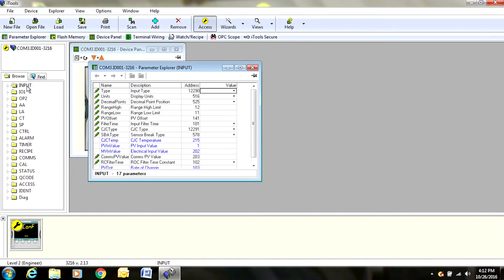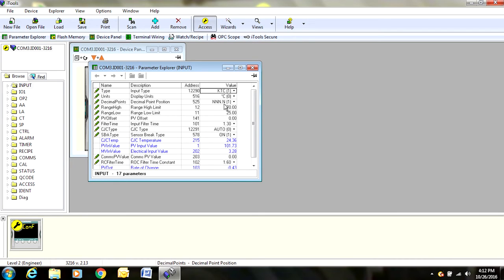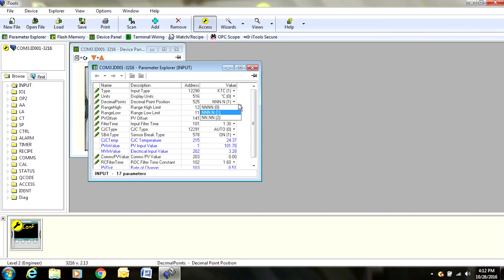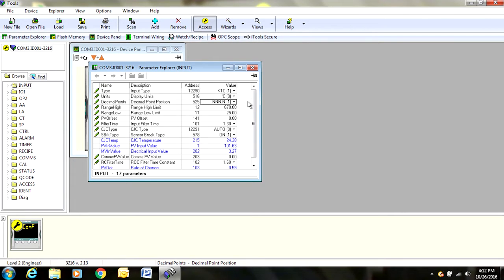We will come back over here to input, double click, and if you notice, decimal points is now black, so we can change that if we would like to go to two decimal points, no decimal points, whatever we need. There is also a range feature. You can set a high range. So if you are only going to calibrate up to maybe 400 degrees, you could set your range to let's say 450.